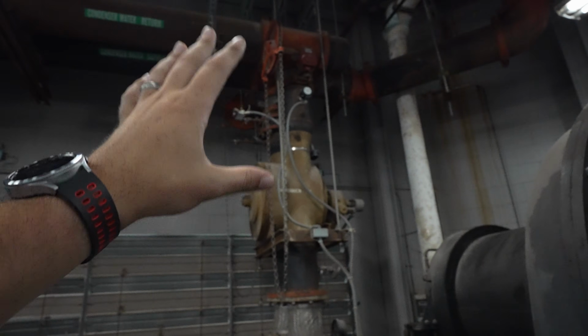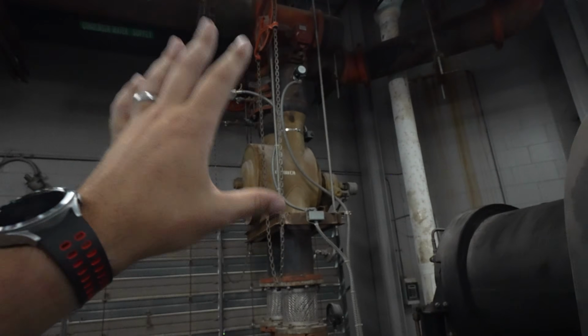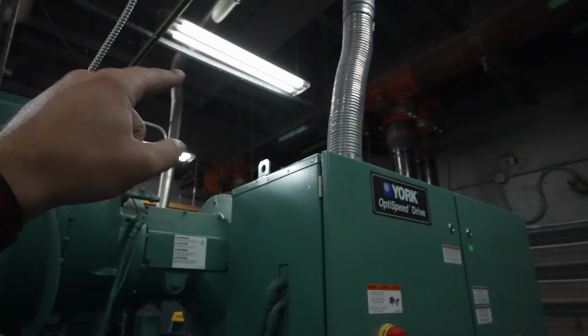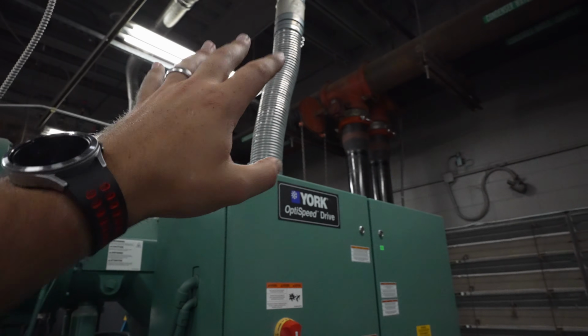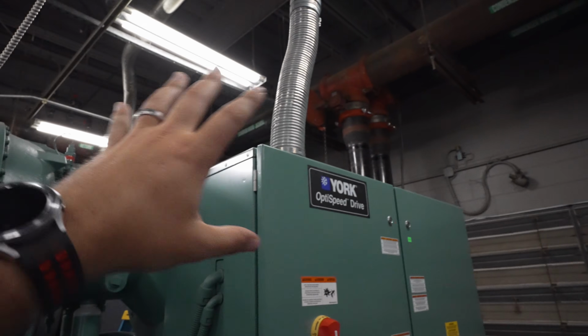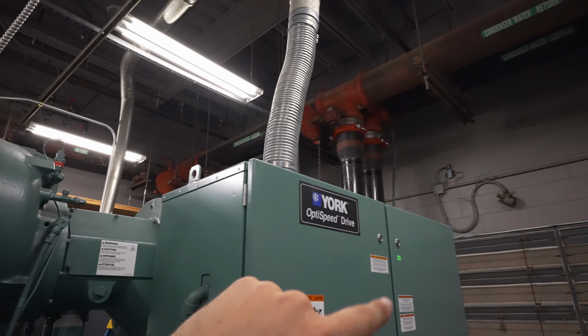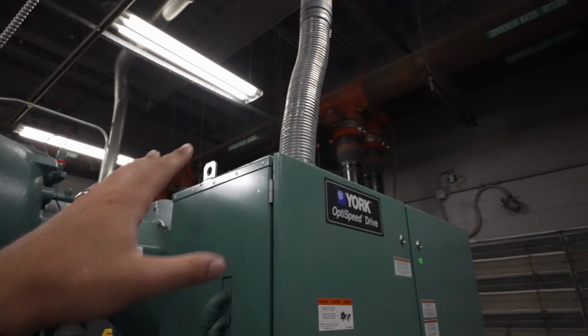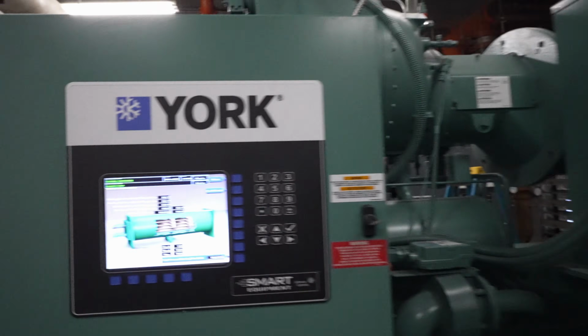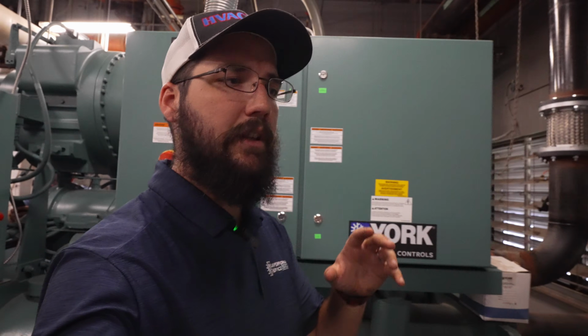Once we got it stable, I was able to isolate this chiller off to where it wasn't going to flow through here any further, and that was going to remove that from the equation. These two do not have ISO control, so that is something that is pretty important if you're going to try to stage your pumps. And I am going to recommend to the customer that they try to get the isolation system functioning on the condenser water side. It does work on the chill water. But hindsight through this whole situation, I genuinely believe that they were dealing with some high head pressure issues or high condenser water temperatures. They were just dealing with issues on the condenser water side. They tried to resolve that by lowering that liquid level, which is a very dangerous thing for this machine.